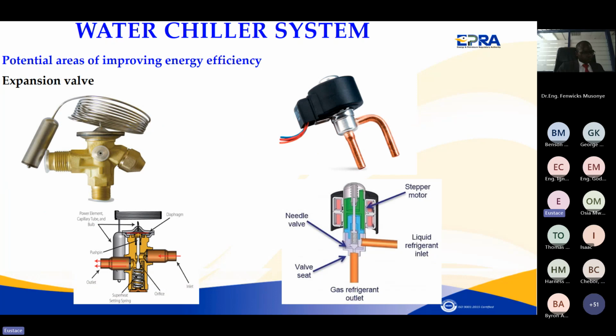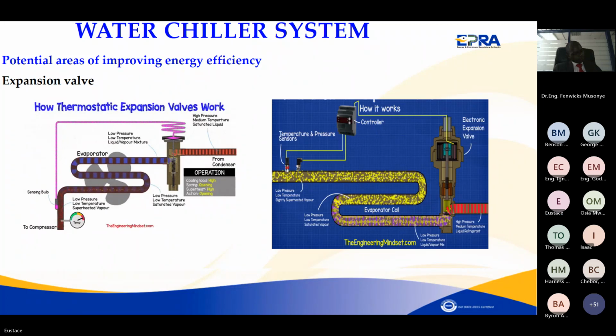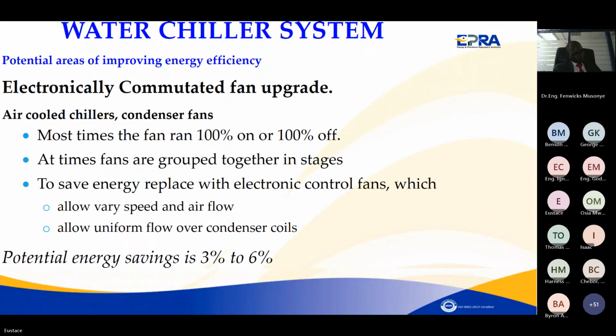The control valves, you can change from thermostatic expansion valves to electronic valves, which have a quicker response, thus saving the time for cooling. The expansion valves are a bit slow, so you improve the response time, either for the refrigeration cycle or the cooling systems. Those are how the thermostatic expansion valves operate. These days they are being replaced by the electronic ones, which will improve the efficiency of the system, because improving the response is good.